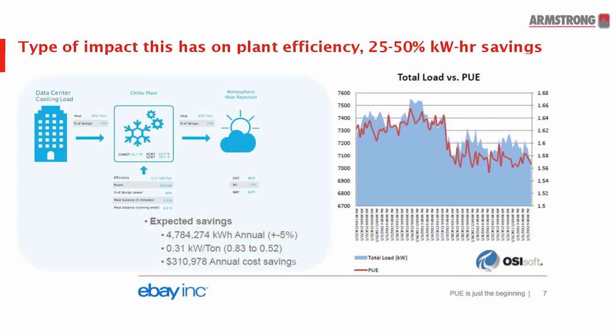What's the impact of this? This is one of the earlier projects we did on a site that's been well documented, and it had a dramatic impact on the PUE. It went from around 1.65 - it was an all variable speed chiller plant to start - and then you can see the step down in performance when we implemented that optimization and learning. So again, thinking about the impact of that PUE improvement on the global environment of our power supply, it's quite dramatic.